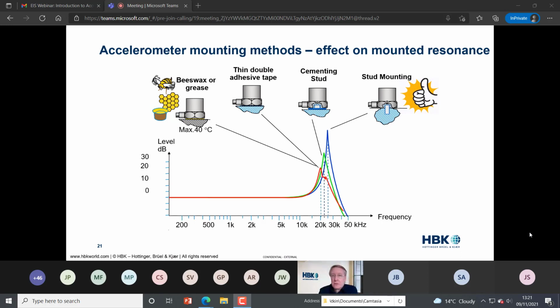Pretty close second to that is to use a cement stud, where you cement the stud down to the surface, then screw the accelerometer onto that. You see that's brought the resonance down a bit. It's also added some damping. And then we've got beeswax, which is fine at low temperatures, or very thin double-sided adhesive tape that can be used, but you see that that has a significant lowering effect on the mounted resonance. So you just need to be careful about this when you're making measurements. You've got to have the accelerometer effectively being a part of the structure to get the mounted resonance that is listed on the calibration chart.